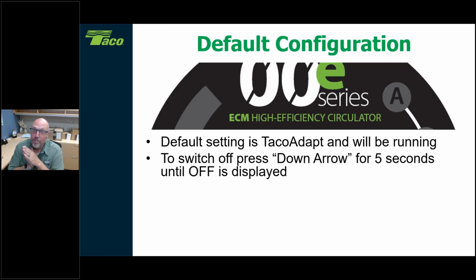So you can turn the pump off, meaning you can disable it so it does not run. What you do is press the down arrow on the circulator itself for 5 seconds, and it will say OFF on the display, and the circulator stops running. That is really useful if you want to start programming this circulator.